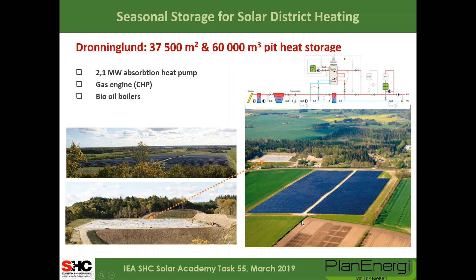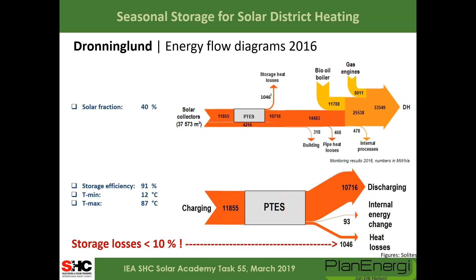Here we have a solar fraction of 40%. And what is very interesting in this case, when you look at the heat balance for the storage, we actually have a storage efficiency of more than 90%, so the heat loss is less than 10%. This is very encouraging - the annual heat loss is only 10% of the energy output. You see here a low minimum temperature, because there's a heat pump lowering the temperature in the storage in winter and springtime, which is part of the explanation for the low storage heat loss.